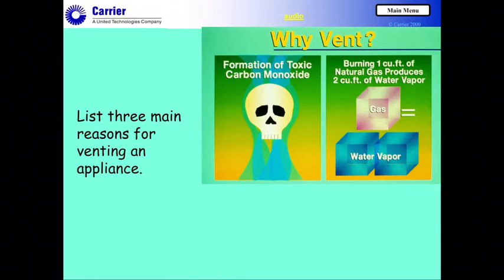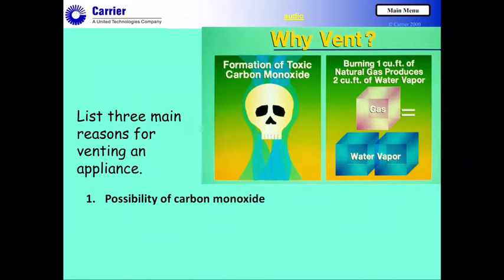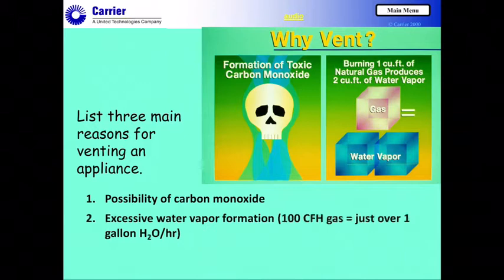Let's take a look at the reasons for venting an appliance — why do we need to do this? There are really three main reasons. One is that there's always a possibility of carbon monoxide being produced, even on well-burning appliances. It's difficult to get perfect combustion with zero carbon monoxide. Another reason is the incredible amount of water that's being formed during combustion.